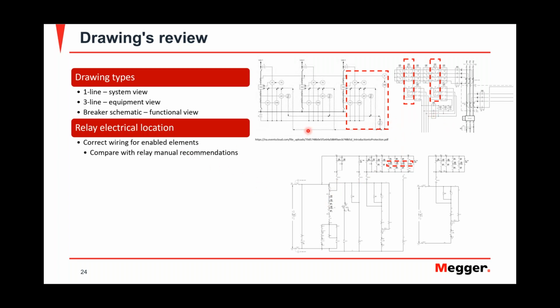In this case, you're looking at the relay. In the one line, this is how the relay is portrayed. In a three line, it's like this. On the schematic, it's going to show you like this, your IO. So depending on what you're troubleshooting, knowing where to look, not only the type of drawing but the location, and having an idea. These are things that you have to keep in mind.